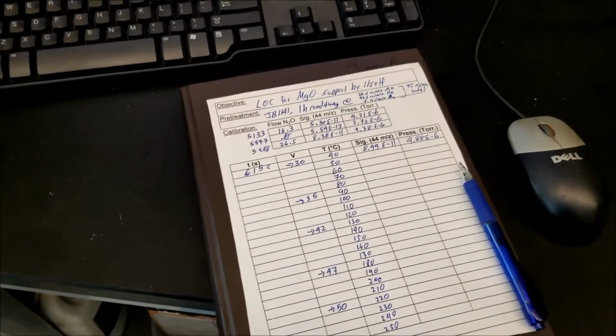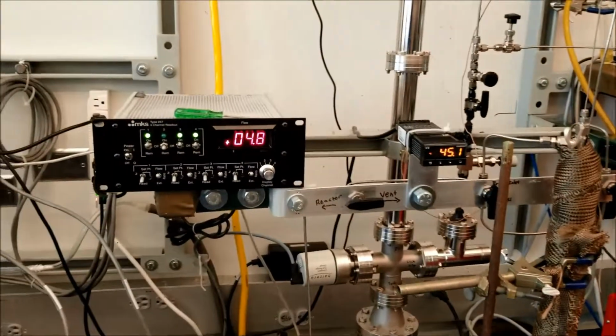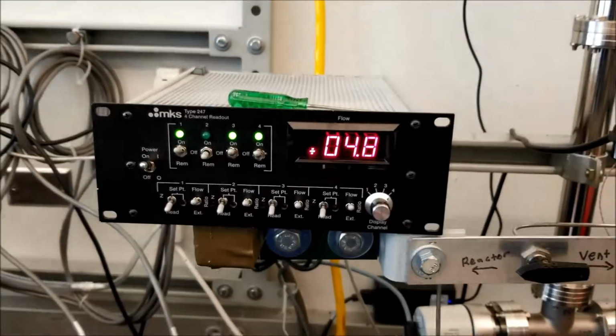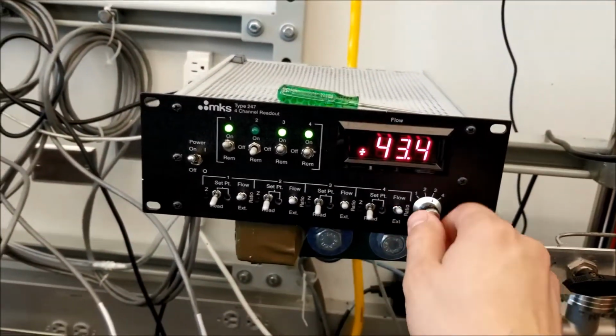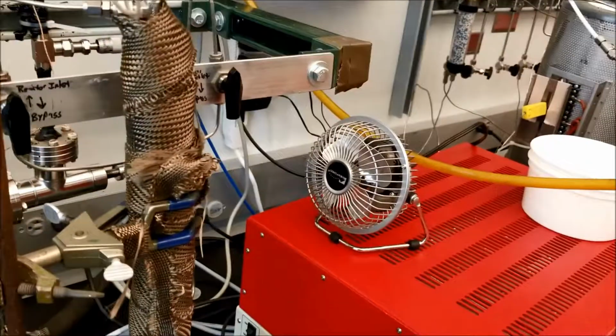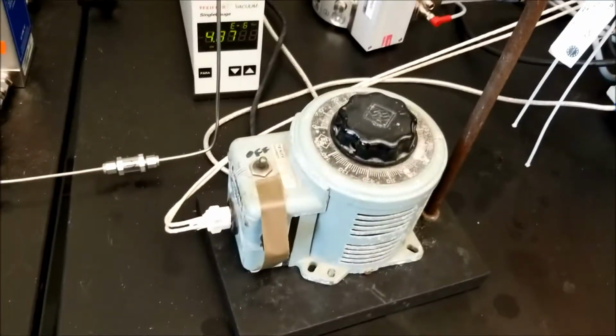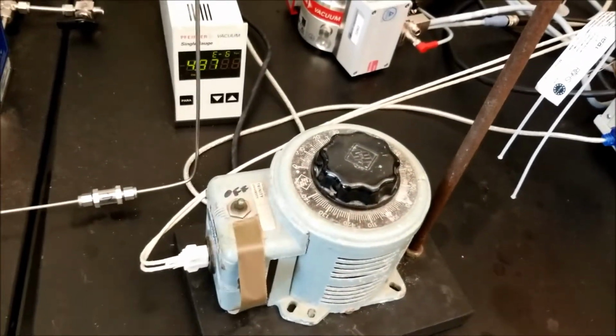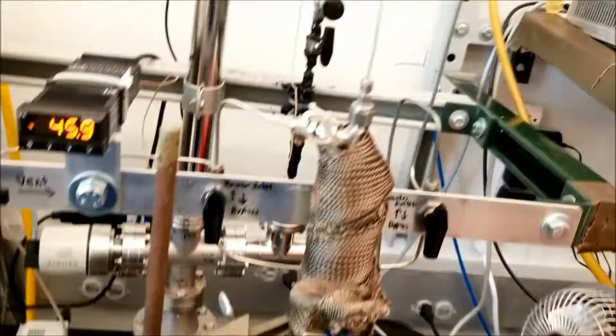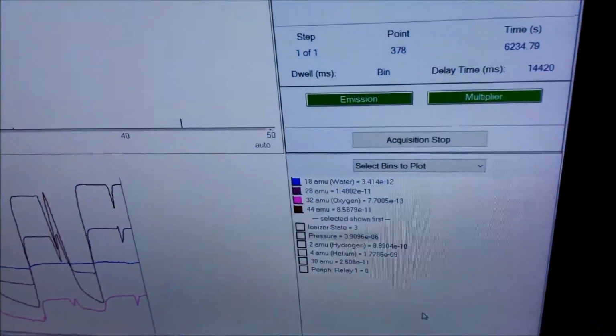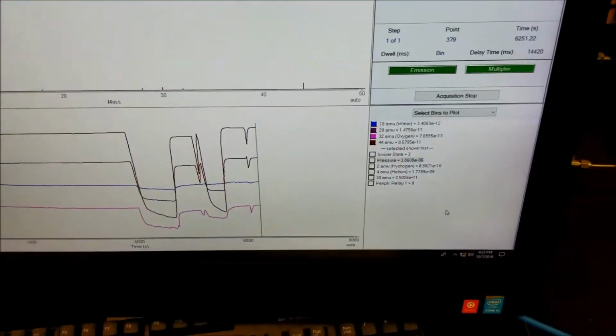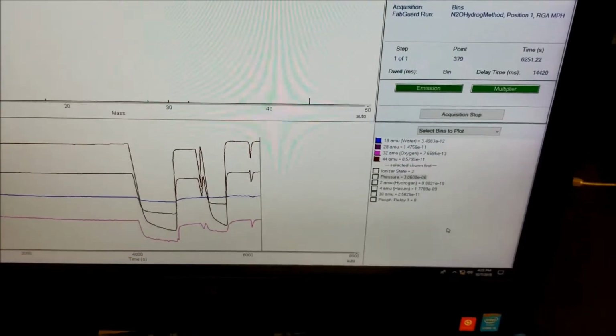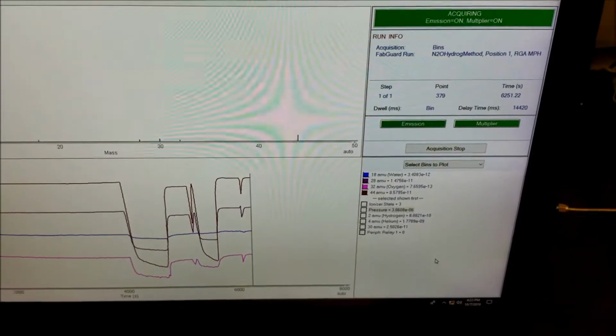But then, much like the kinetics video, you're going to follow the same shutdown procedure as before, where you'll turn off the N2O and the hydrogen, and then flow 100 milliliters a minute of the helium through the reactor while the fan is on and cooling, and the variac is set to 0. At that point also, you'll close the valve for the vacuum chamber, and click acquisition stop on the RGA itself. All right, I'm going to get to this.